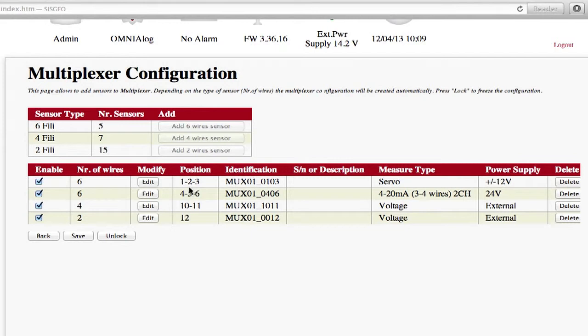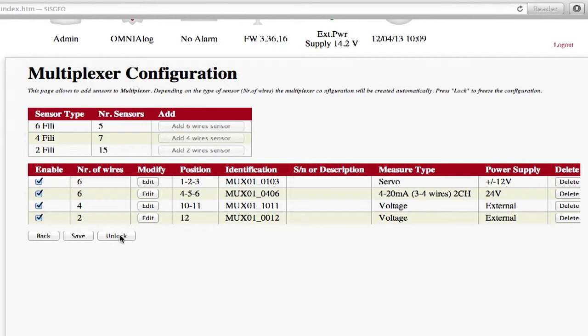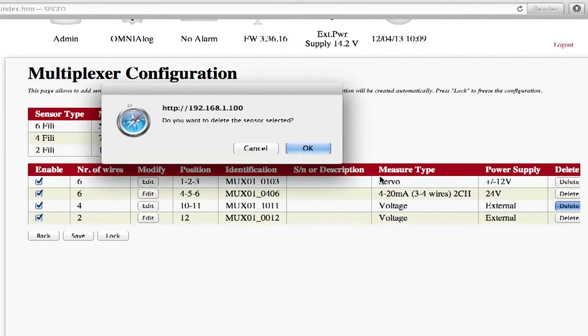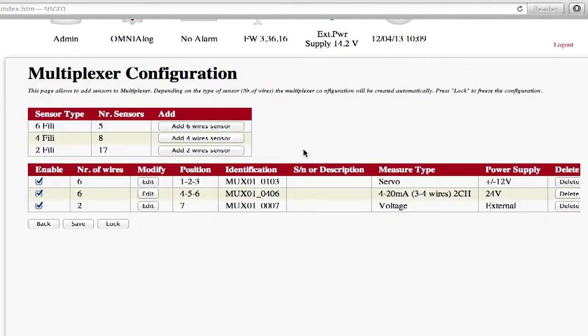The configuration is unblocked by pressing the Unlock button, and once more it will be possible to add new instruments. For example, removing the instrument connected to position 10, 11 changes the positions of the previously configured instruments and causes them to occupy the free positions. For example, the instrument that was connected to position 12 is relocated to position 7. Before leaving the page, press Save to confirm the changes carried out.